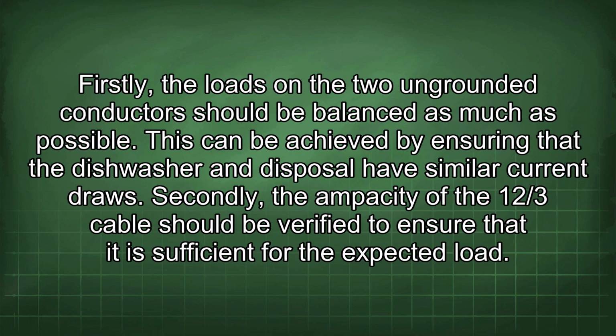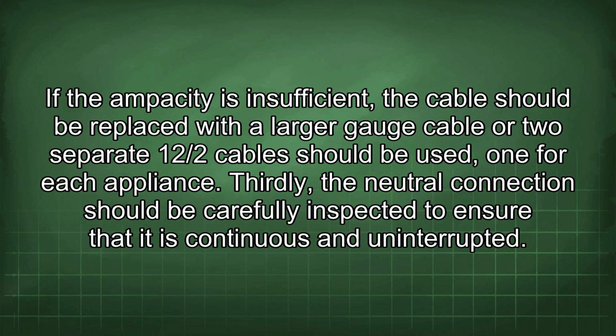Firstly, the loads on the two ungrounded conductors should be balanced as much as possible. This can be achieved by ensuring that the dishwasher and disposal have similar current draws. Secondly, the ampacity of the 12/3 cable should be verified to ensure that it is sufficient for the expected load. If the ampacity is insufficient, the cable should be replaced with a larger gauge cable, or two separate 12/2 cables should be used, one for each appliance.